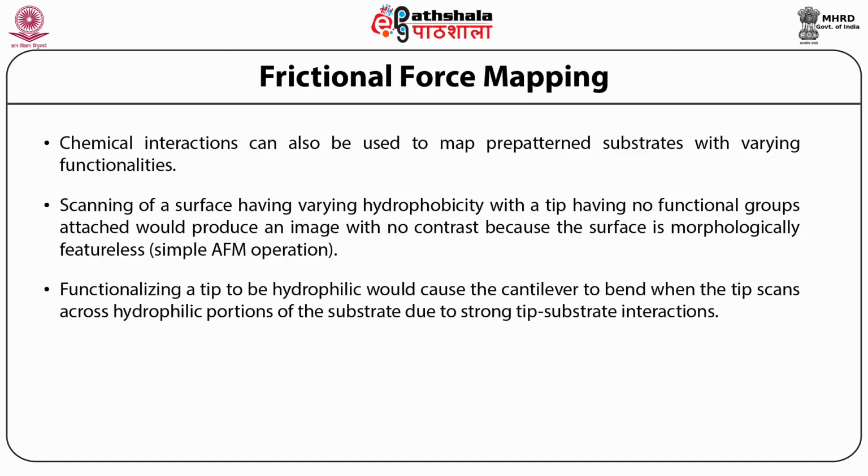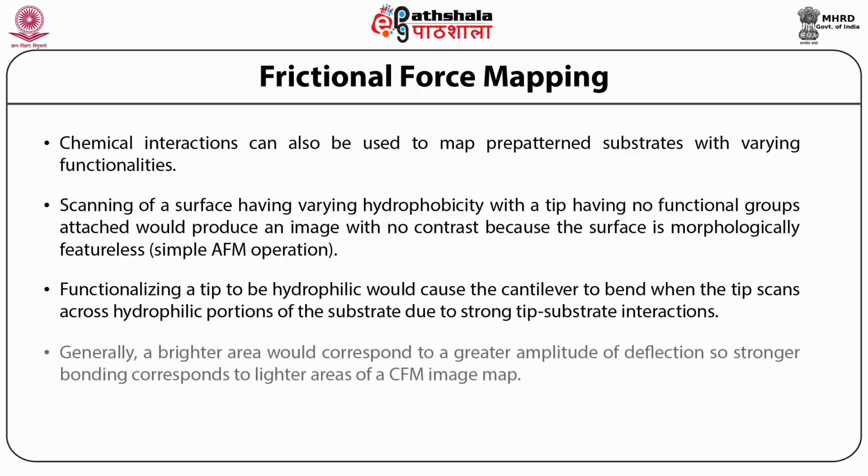Functionalizing a tip to be hydrophilic would cause the cantilever to bend when the tip scans across hydrophilic portions of the substrate due to strong tip-substrate interaction. This is detected by laser deflection in a position-sensitive detector, therefore producing a chemical profile image of the surface.